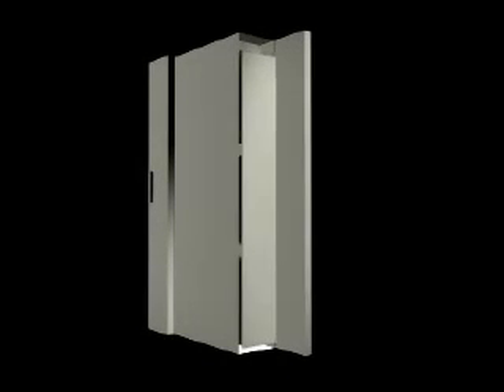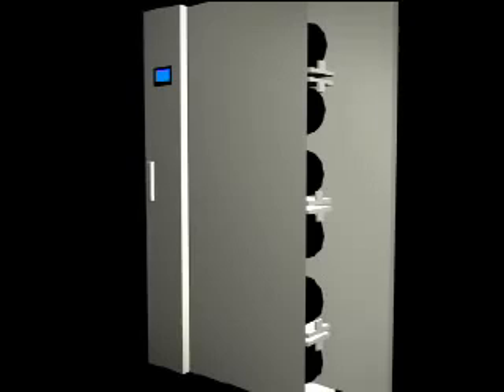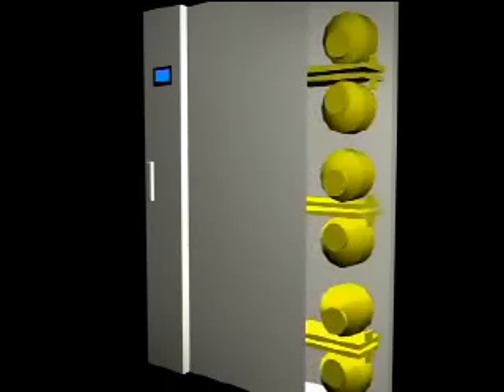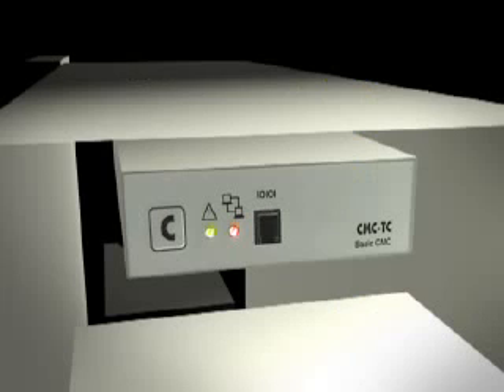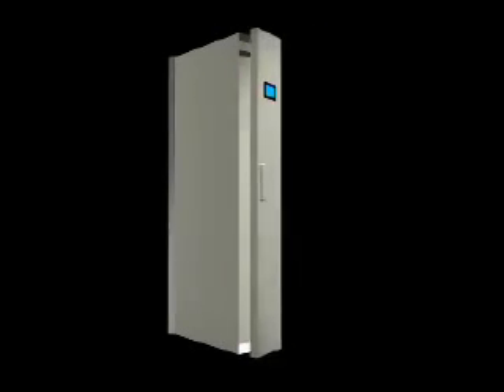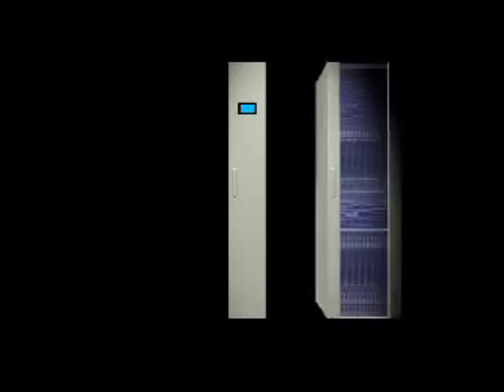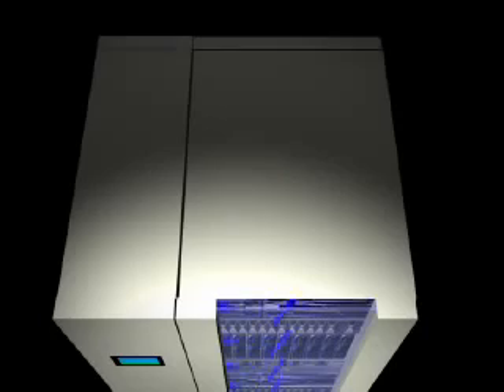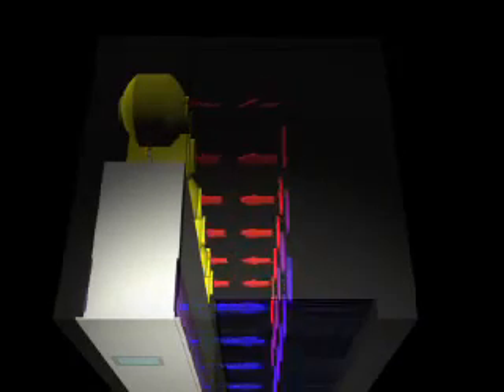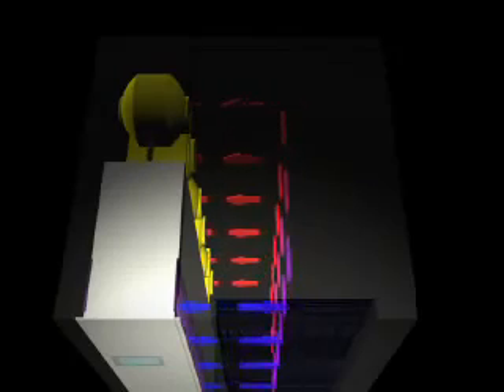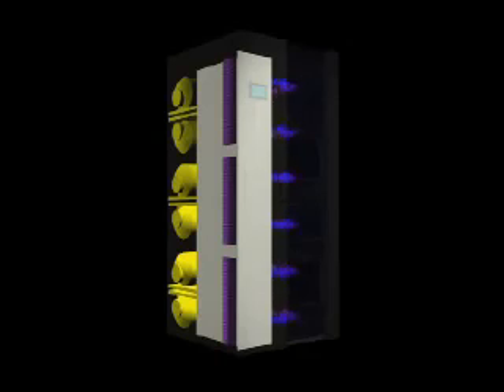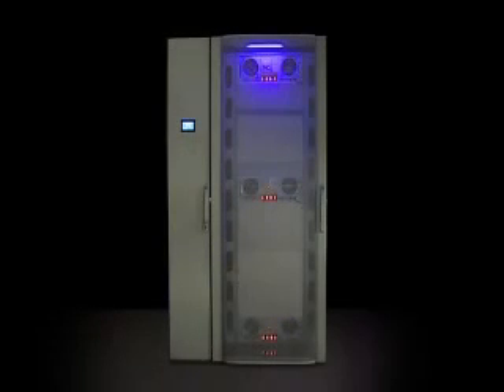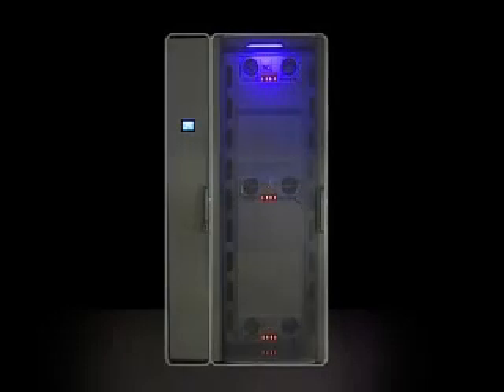The LCP Plus 300mm wide module consists of a heat exchanger fed from an external chiller system and 6 fans, which circulate the hot air via the heat exchanger. Intelligent modules monitor the fans and the flow rates and are displayed on a touch-sensitive LCD screen on the front of the LCP Plus. The LCP Plus is connected to a standard 1200mm deep enclosure and pulls the hot air from the server exhaust and cools the air via the heat exchanger. It's been specifically designed to blow cool air across the whole height of the enclosure to ensure that there's no chance of having any hotspots developing. This is a closed-loop cooling system, which focuses the cooling directly where it's required.